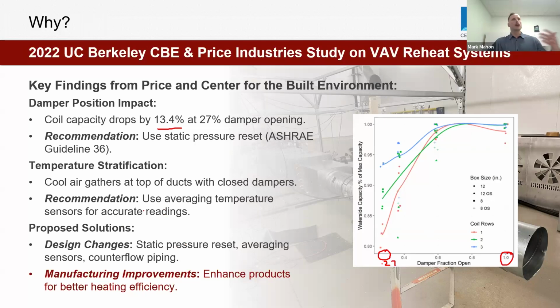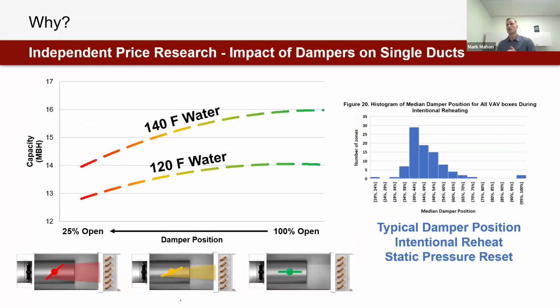They noted a big risk of temperature stratification. So sometimes with that mixing element being a damper, directly upstream of a VAV box, we're going to get a lot of temperature stratification downstream, which could be problematic for single point discharge air temperature probes. And what they really proposed was we need to continue to revisit and improve static pressure reset sequencing on buildings. We should use averaging DATs. And then they left this as an open-ended question, saying, which manufacturer is going to make a product that works better for this? And so that was the scope of my work.